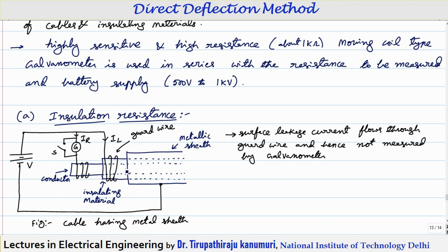Between the conductor and the metallic sheath there is an insulator. Whenever you give the supply, because this is nothing but two plates — the outer metallic sheath acts as one plate, the conductor acts as another plate, and in between there is an insulator — it automatically acts as a capacitor. Whenever a capacitor is suddenly connected, it will start charging because that displacement current will start passing through it.